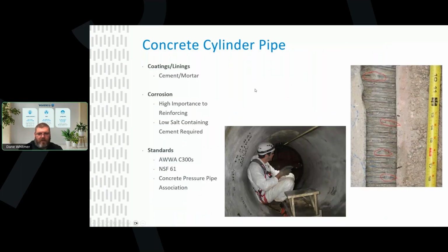It's really important that you provide regular maintenance on these pipes, and that involves inspections. So here's an example of an inspection for the bar wrap, and there are multiple breaks in that wrap. If this isn't a pre-stressed condition for this bar wrap, that's where you're losing the strength of the pipe. And if this pipe has a high pressure, it may not be able to withstand that pressure any longer, and that pipe would have to be replaced.